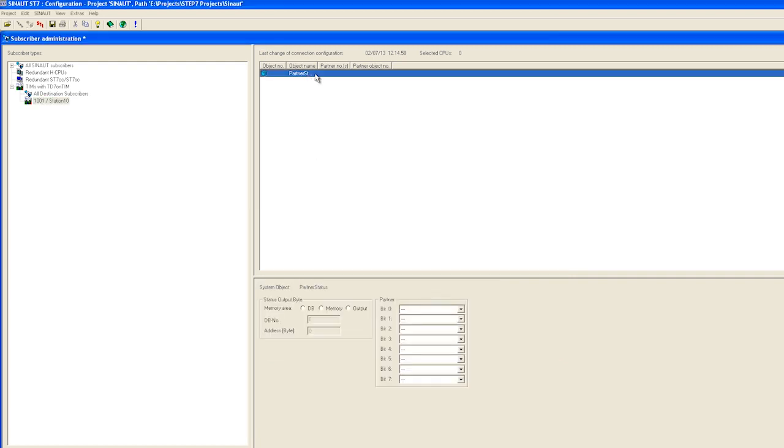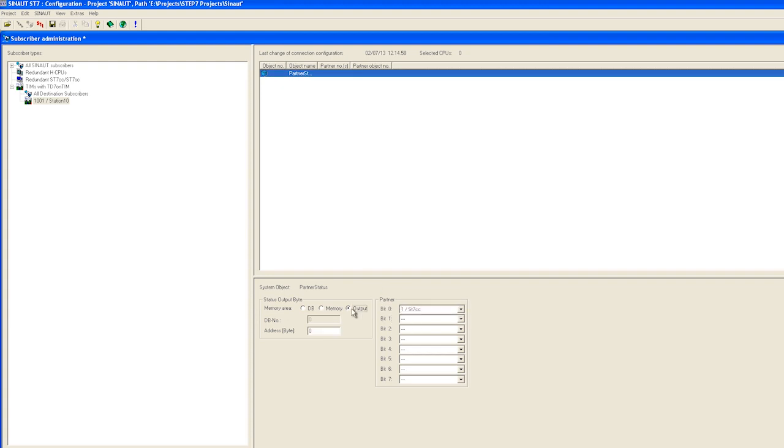The partner status is a block that monitors communication with the control center and can display it on the CPU. We select the partner to be monitored. This is our ST7 CC control center and output the connection status, for example directly to a digital output module. In our project this module has the output byte address 128.